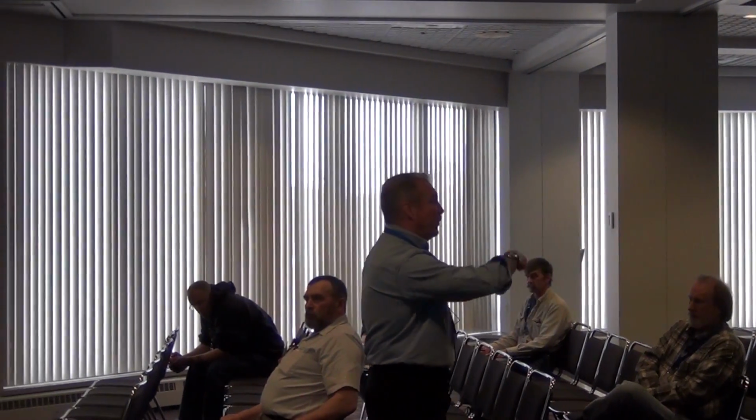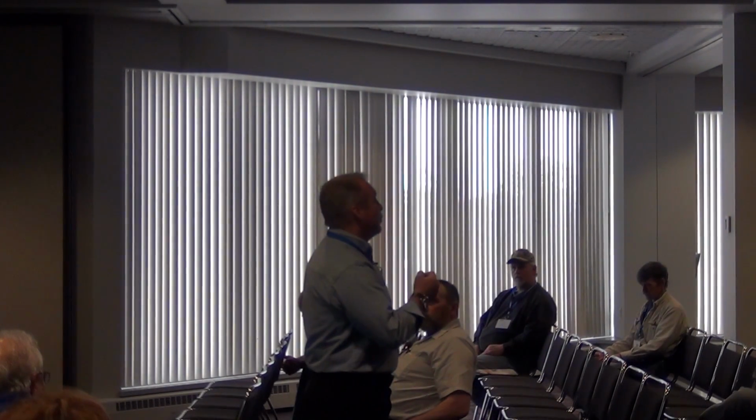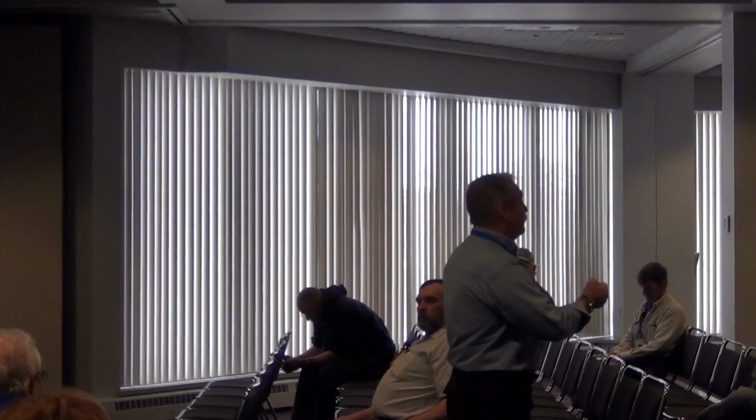This building here has large ductwork. If I have a door on my ductwork, is that a confined space? Yes. Now when I go in there, I better turn off the fan, correct? Because of getting chewed up by the fan, yes? So I have an isolation issue. But I propose to you that we do not have a reasonable potential for poor air quality, correct? Would you agree? Therefore, it is a non-permit required confined space.